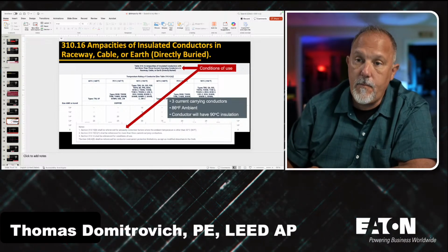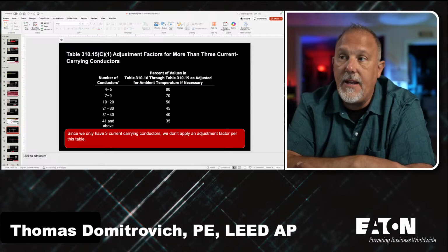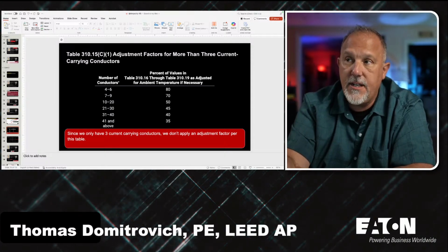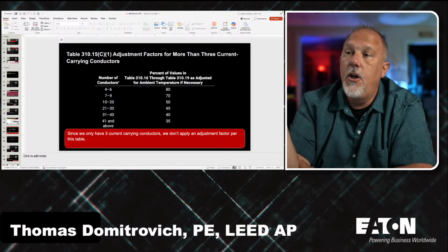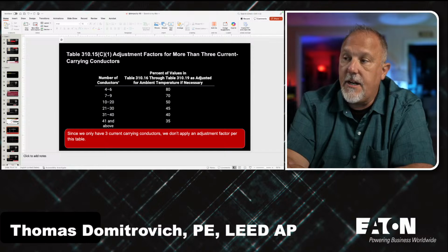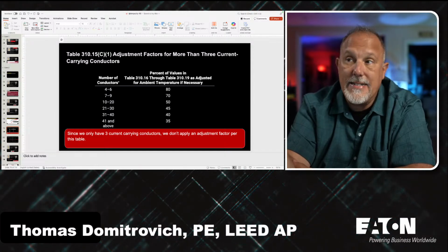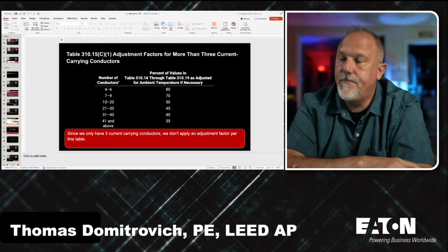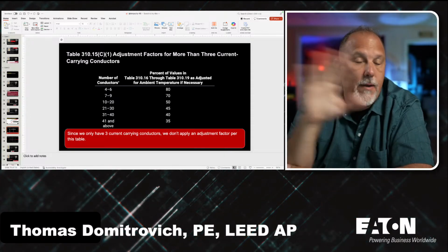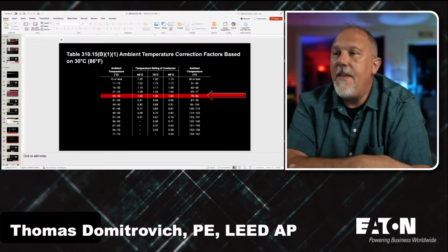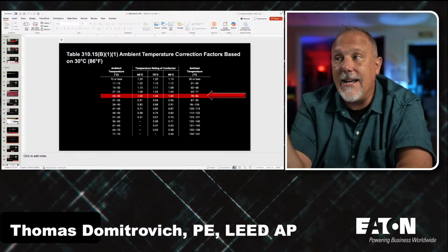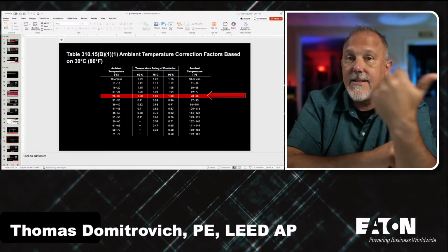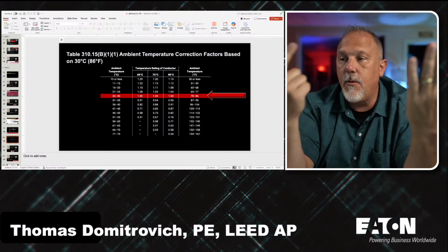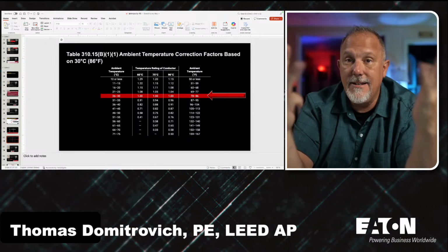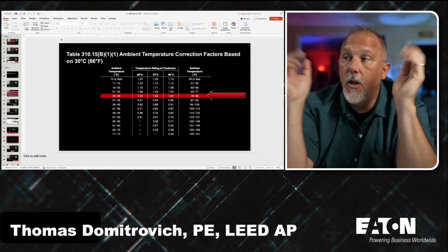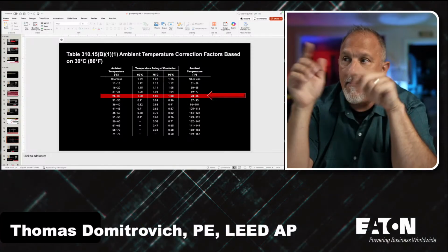All right, so what that means is if I go to 310.15, I don't have to do any percent values or multiplying factors because of the 3 current carrying conductors. So I don't have to apply an adjustment factor per that table. Okay, I'm good with that. And then on the ambient, we said we were 86, but I know I have a range. So I've got 78, 79, 80, 81, 82, 83, 84, 85, 86. I've got 9 degrees of latitude, of wiggle room, where I have a 1.0 multiplier. I'm at the top end of that.